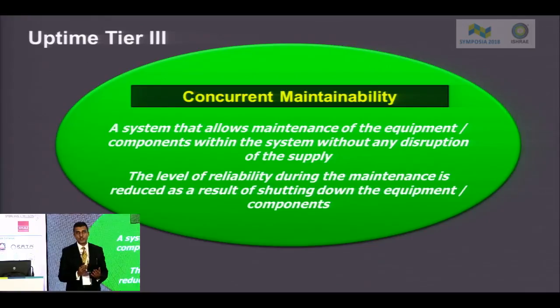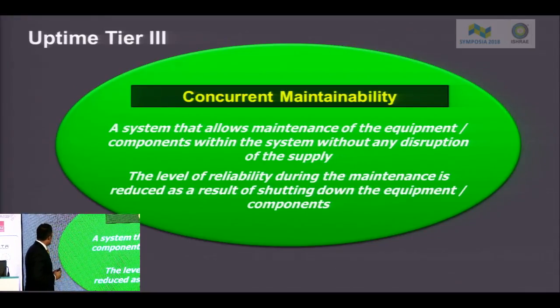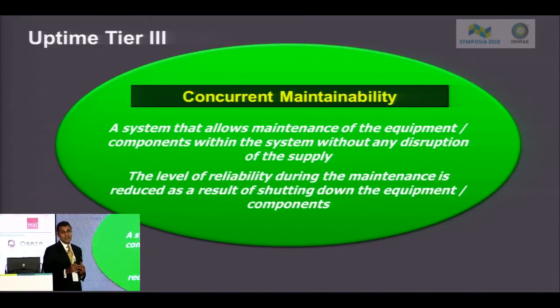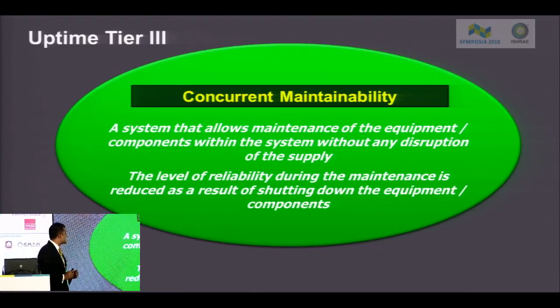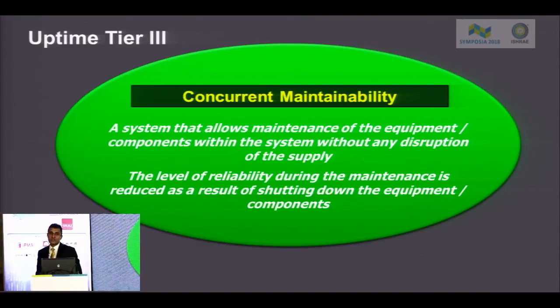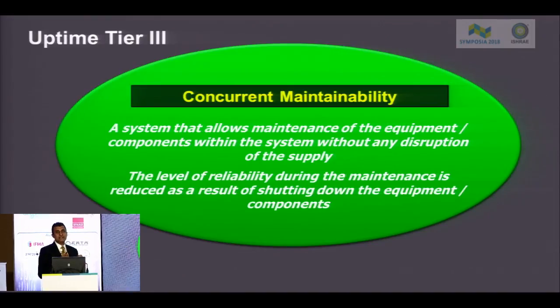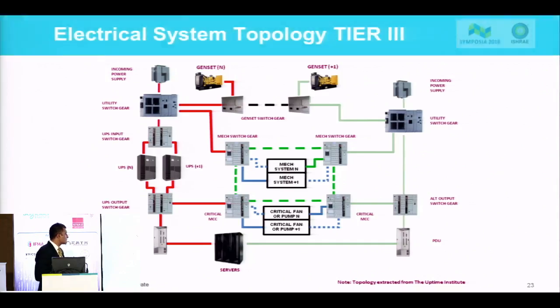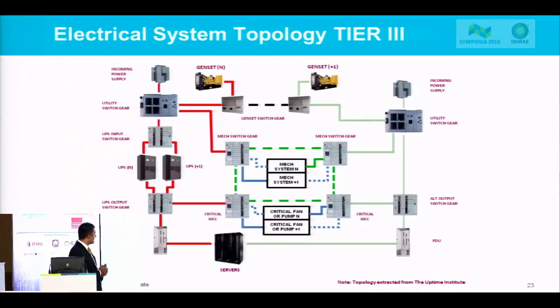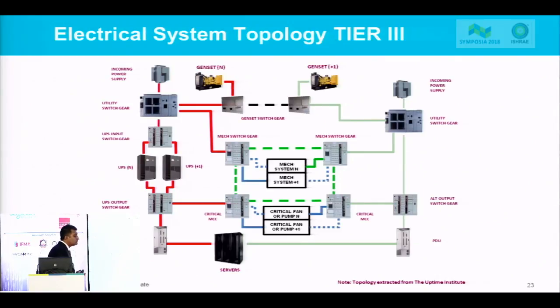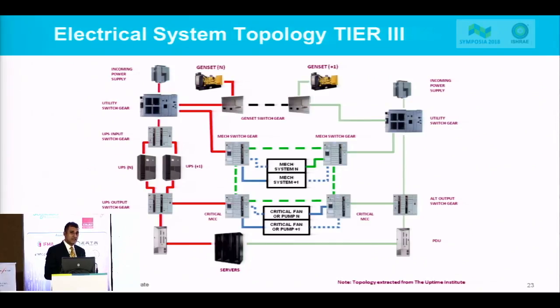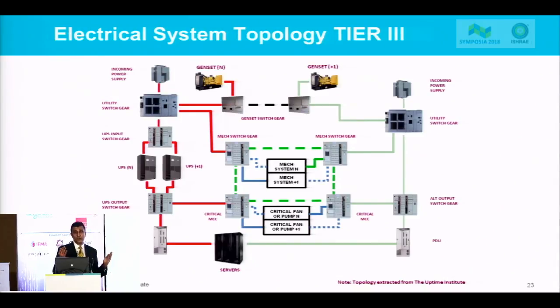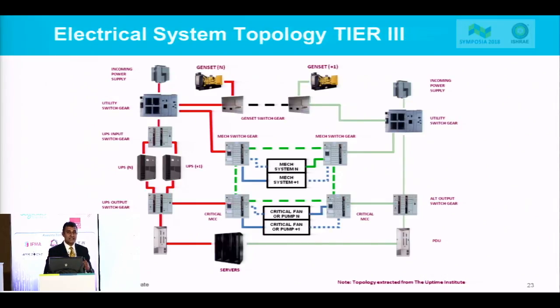So let's have a look at some of the topologies that we have in the data center field. What is very common in terms of reliability is the Tier 3 Uptime Institute certified data center. So this data center offers concurrent maintainability. That is to say that any component within the data center can be serviced without interrupting the load to the IT equipment. So this is just to depict what it actually looks like. We have on the right side of the screen a normal supply, and on the left side of the screen is an uninterruptible power supply. Okay, so you have one on UPS and another feed on normal supply. They're tied in by a bus, so the IT rack sees two UPS supply. The UPS run at almost 100%.